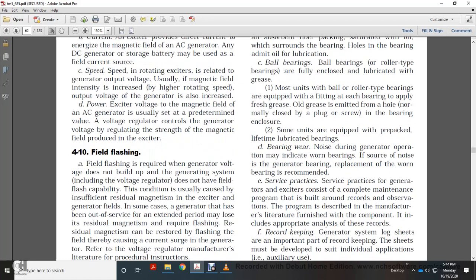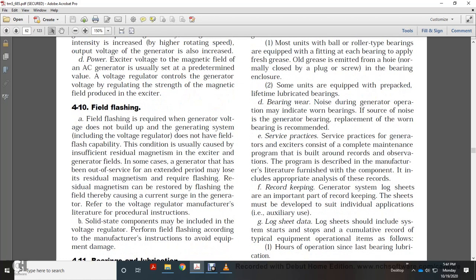Bearing wear and noise during generator operation indicate wearing of the bearing. Some noise from the generator bearing calls for replacing the worn bearings as recommended. Service practice with the generator exciters considers a complete maintenance program built up around an observation program, with the manufacturer literature furnishing the component information.